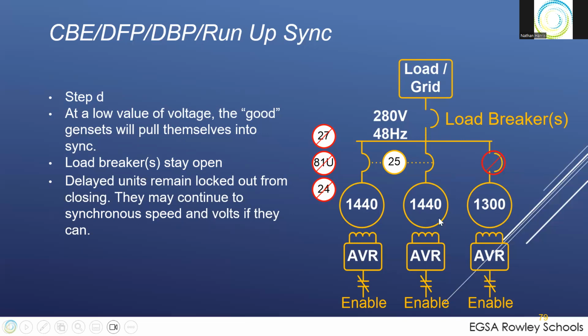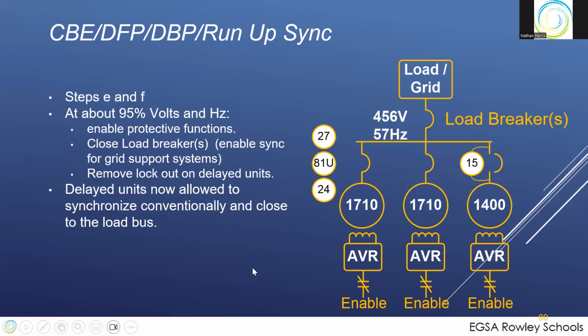You can't run. We're going to run these two. When you get to about 95% volts, so 456 is 95% of 480, 57 hertz, 95% of frequency, you say we're good to go. Turn on your protection. Your 27 under voltage is turned on. Your 81 under frequency is turned on. Your 24 volts per hertz, those are all turned back on again, and your load breaker is closed. So protection on, generators on, breakers on, loads being fed.